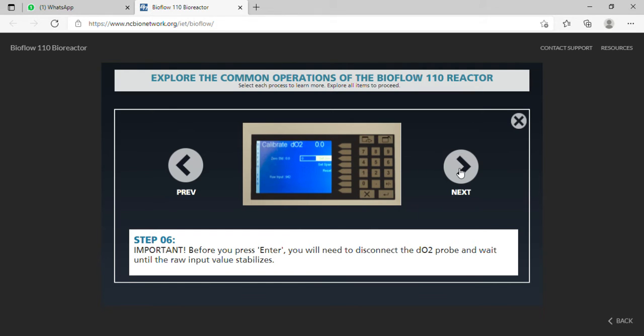Step 6. Important. Before you press enter, you will need to disconnect the DO2 probe and wait until the raw input value stabilizes. Step 7. After the raw input value has stabilized, press enter to accept your set 0 value. Step 8. You may now reconnect the DO2 probe, then select set span to continue with calibration. Step 9, which is to enter the number 100 on the PCU touchpad.